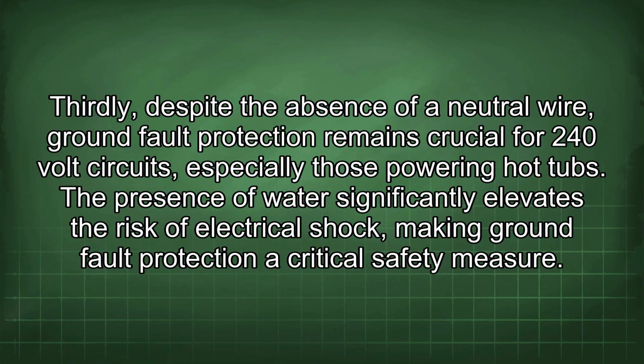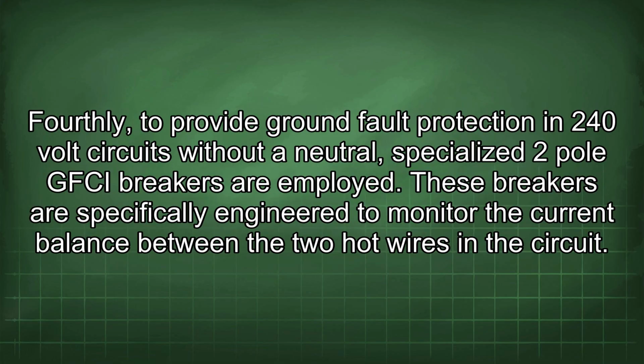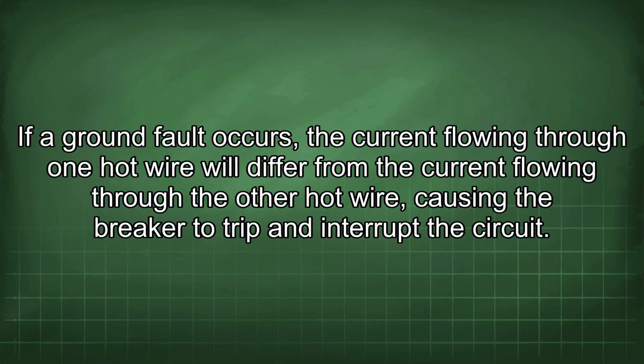safety measure. Fourthly, to provide ground fault protection in 240-volt circuits without a neutral, specialized 2-pole GFCI breakers are employed. These breakers are specifically engineered to monitor the current balance between the two hot wires in the circuit. If a ground fault occurs, the current flowing through one hot wire will differ from the current flowing through the other hot wire, causing the breaker to trip and interrupt the circuit.